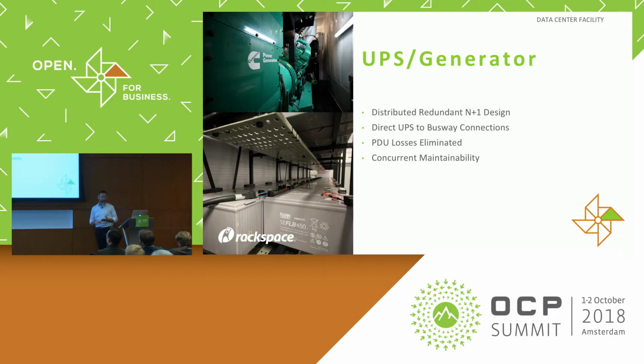The UPSs and generators are also deployed in an N+1 distributed redundant fashion. They're mounted on the roof above the IT equipment. This allows us to connect the UPS output boards directly to the busway distribution in the space, eliminating the use of any isolation PDU or additional wire length. This reduces the electrical losses for that wire, as well as the CapEx for deploying those additional PDUs and infrastructure. So, sort of a simplified design.